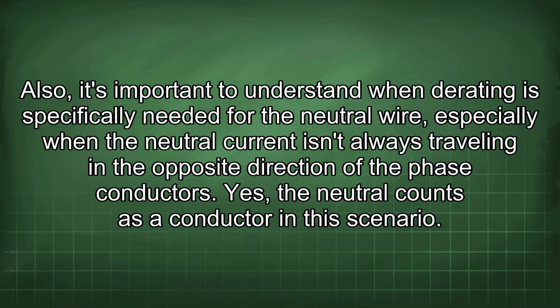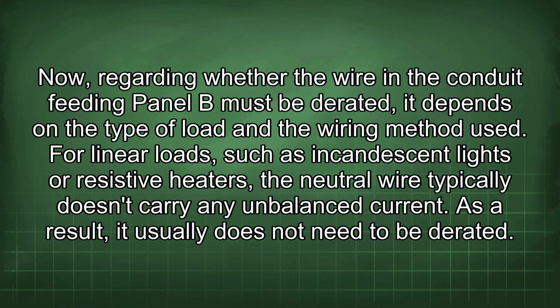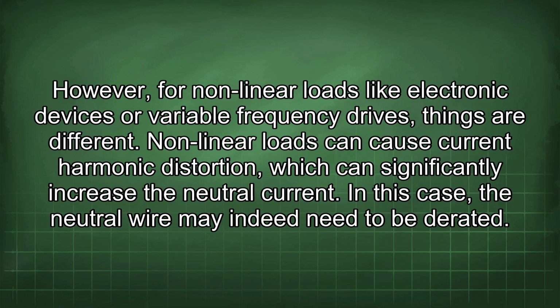Yes, the neutral counts as a conductor in the scenario. Now, regarding whether the wire in the conduit feeding panel B must be derated, it depends on the type of load and the wiring method used. For linear loads, such as incandescent lights or resistive heaters, the neutral wire typically doesn't carry any unbalanced current. As a result, it usually does not need to be derated. However, for nonlinear loads like electronic devices or variable frequency drives, things are different. Nonlinear loads can cause current harmonic distortion, which can significantly increase the neutral current. In this case, the neutral wire may indeed need to be derated.